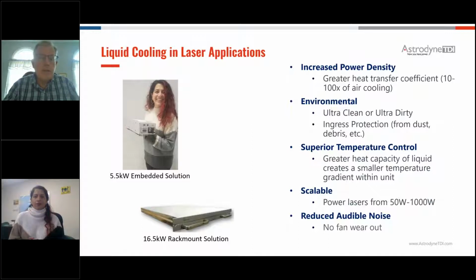Early on when we started with liquid cooling, these solutions were very monolithic, and it was difficult to size the power supply properly for the application. So we've evolved to provide scalable solutions, anywhere from low power, but typically for liquid cooling you'll see it in the 1 kilowatt-plus range up to hundreds of kilowatts. You can see Tamanna there holding one of our 5.5 kilowatt solutions - that's 480 volt input, 60 volts, 5.5 kilowatts output. You can connect those in parallel or series to support different voltage requirements, giving a very effective building block for realizing ultimate system requirements.